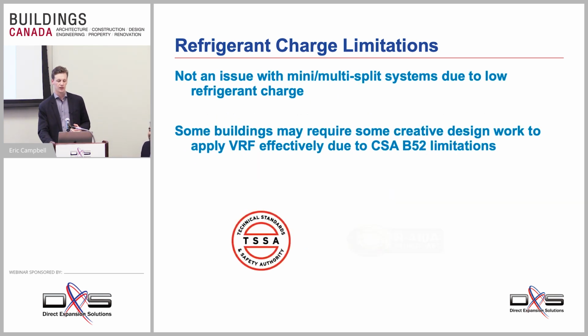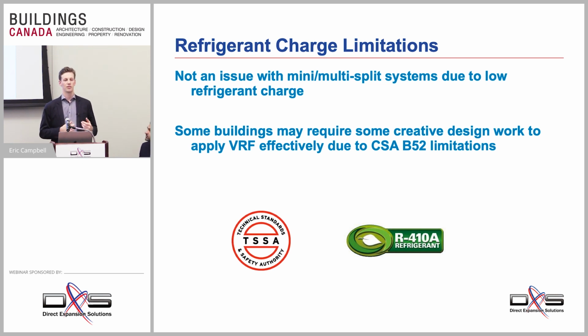And so what this means for us here is that with that 26 pounds per 1,000 cubic feet, any mini split or multi split is going to have in the range of a few pounds, like 5 pounds maximum. So you're never going to run into this type of issue. VRF systems, we do in some cases have to design creatively to get around that. We can't just do whatever seems like the optimal economical solution, and we need to come up with ways to still meet CSA B52 and have a system that is CSA B52 compliant, and meet all the codes while still being an economically feasible system. That's something that's part of the service we provide. And again, as an extra note here, TSSA does certify all these refrigerant-based systems over 5 tons for air conditioning. So you have that as an extra guarantee.